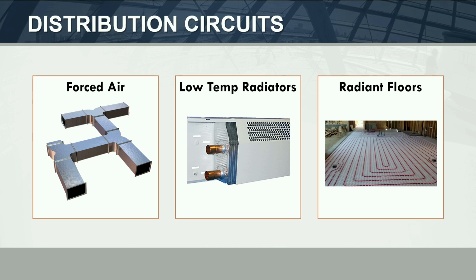Well, in most retrofit applications, you might have a traditional air conditioning system and a traditional oil-fired boiler with baseboard, right? And then retrofitting that, okay, you put in a split system, but obviously there's zoning issues, there's other issues with an air conditioning design system for heating, whereas a house with baseboard heat might have multiple zones. It might be a simpler, better application, is what I'm driving at, to produce the hydronic heat through the water-to-water system and replace all of the baseboard in the house with this low-temperature radiation, and then just change your air handler into a chilled water coil system. Does that make reasonable sense? People do systems like that all the time. That makes sense. Thank you.